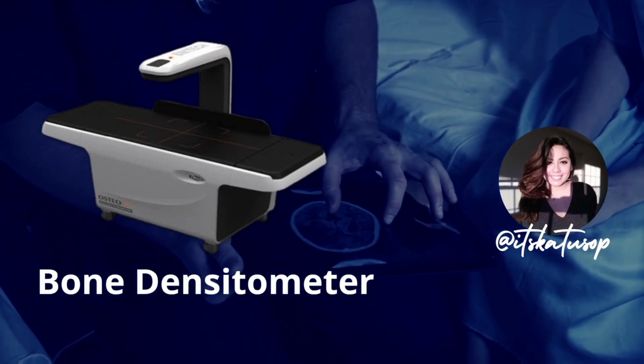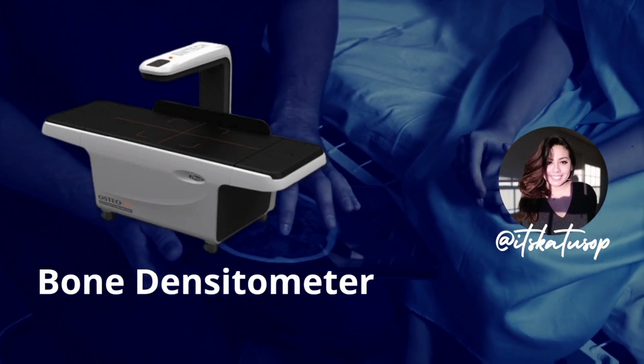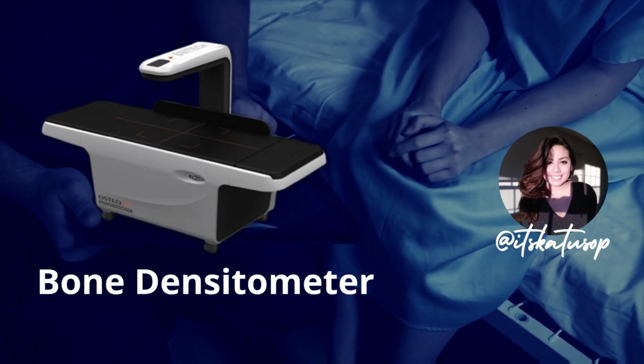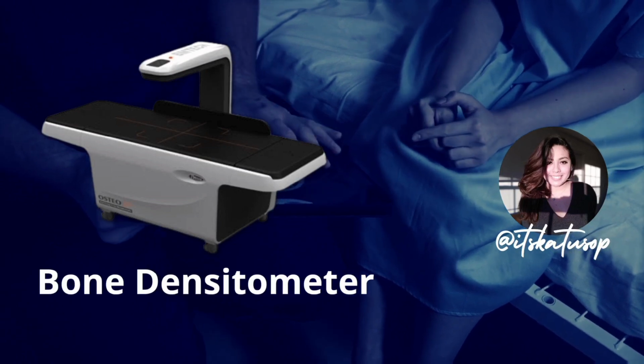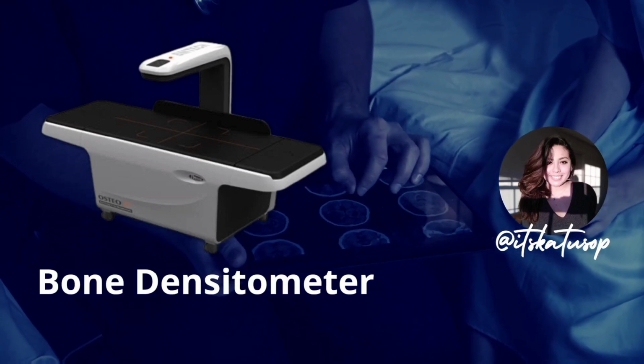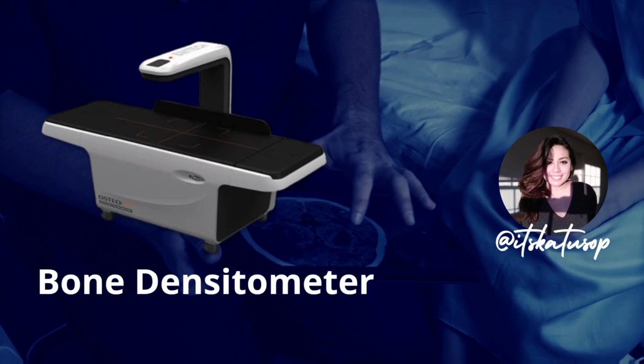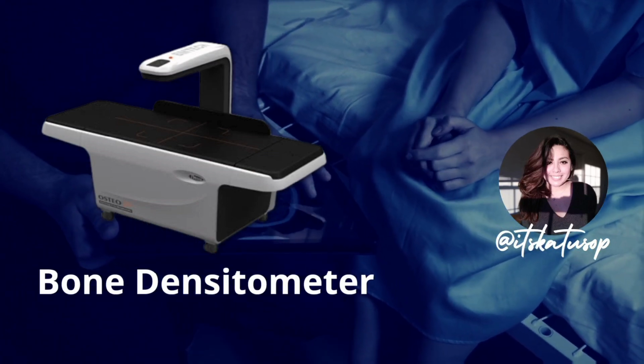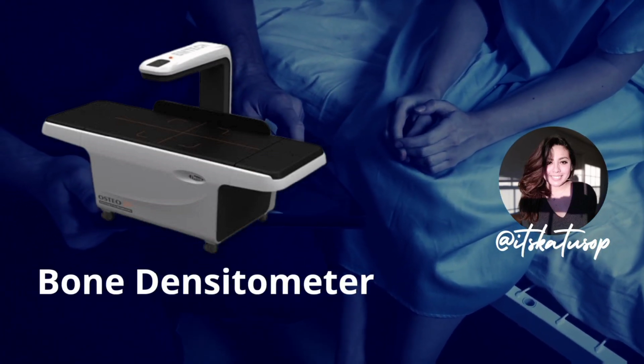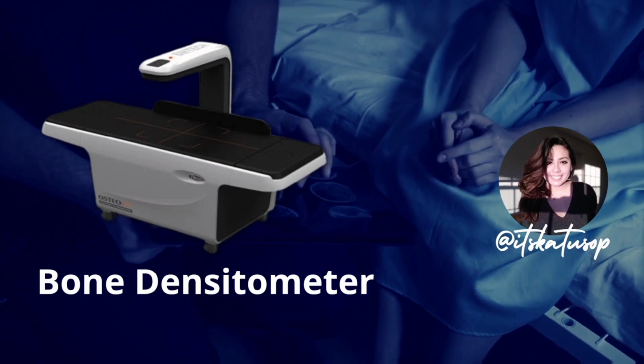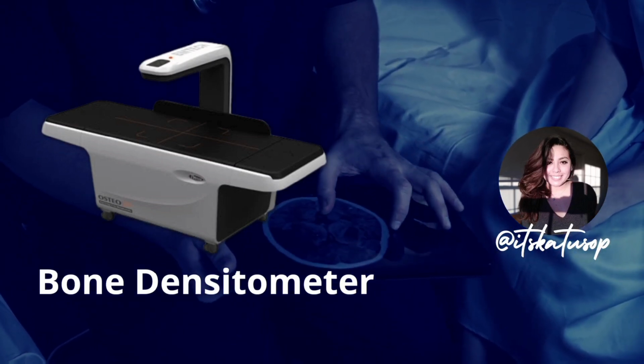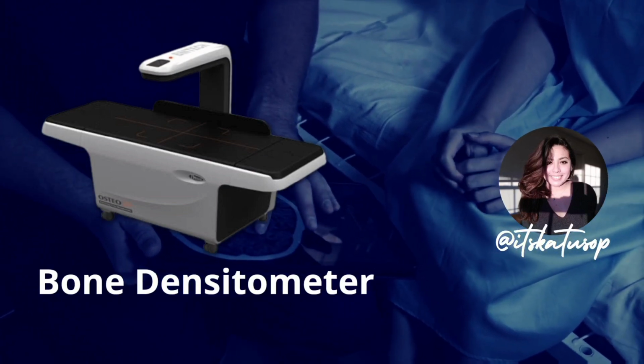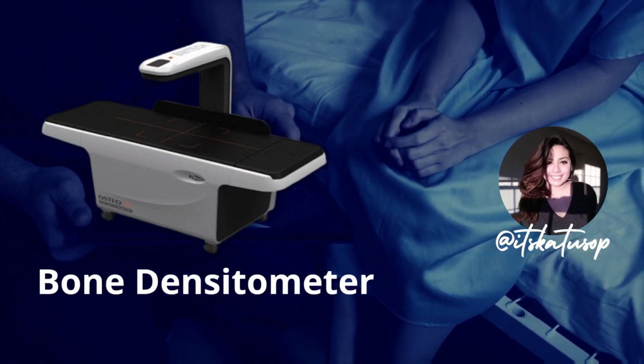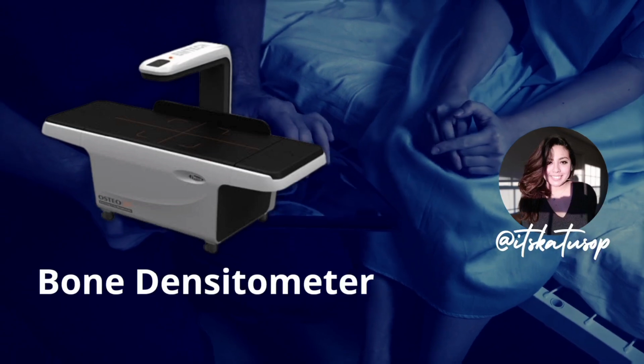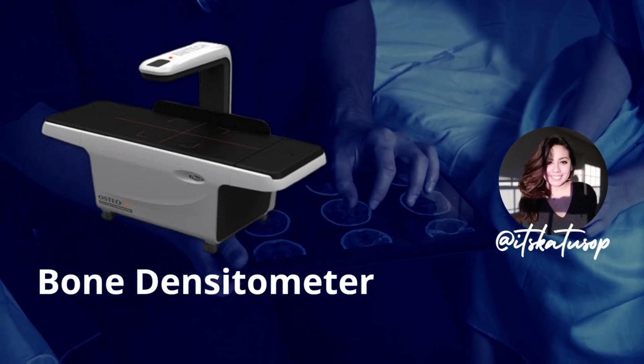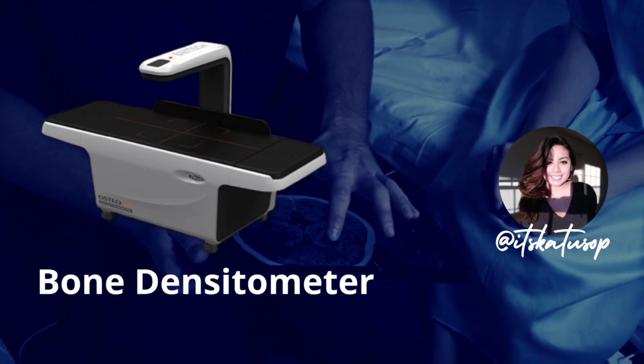A DXA scanner works in the following manner. It uses low-dose X-rays to produce images of the bones. These X-ray beams pass through the bones, and the amount of X-ray that is absorbed by the bones is what is being measured. The denser the bones, the more X-ray is absorbed. Pretty logical.